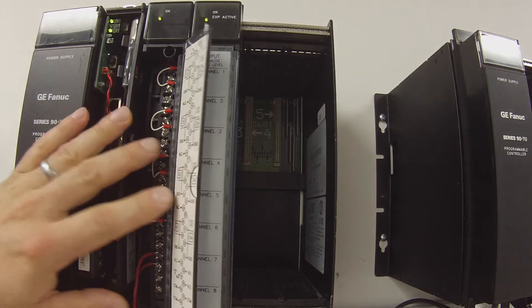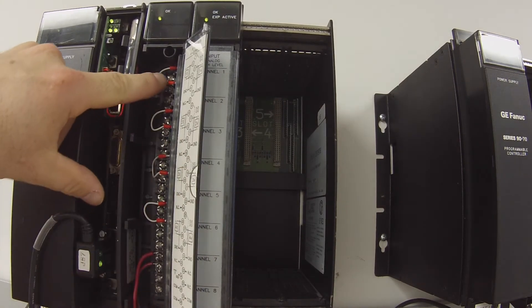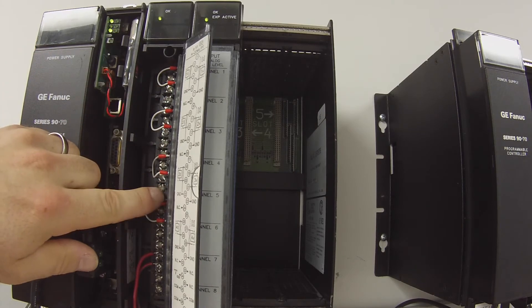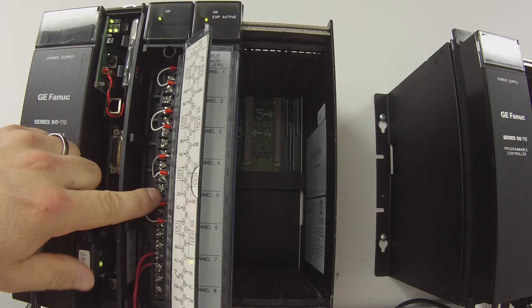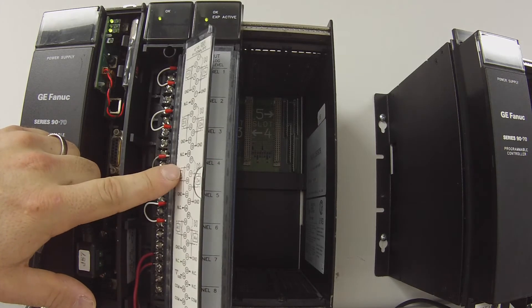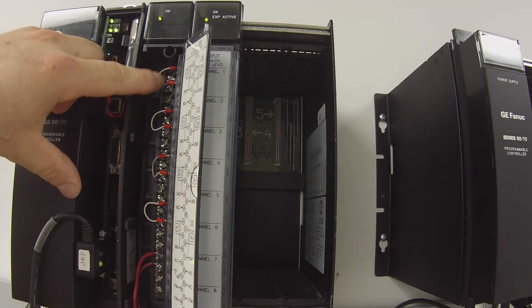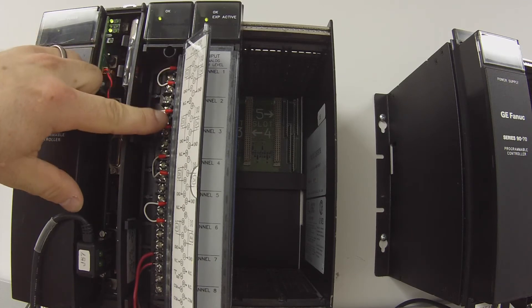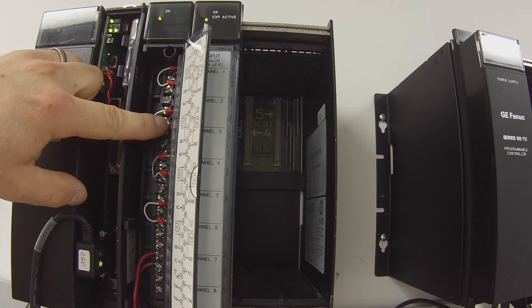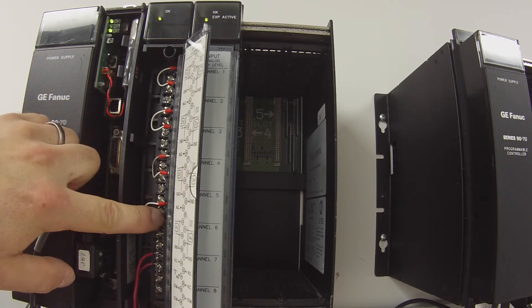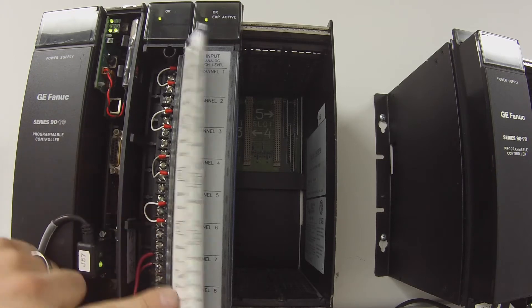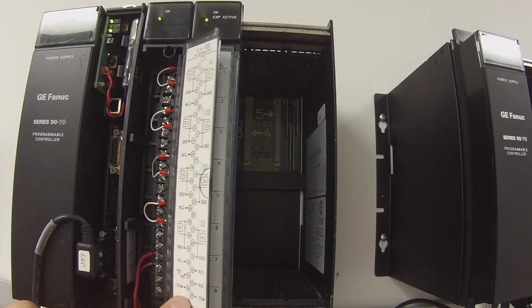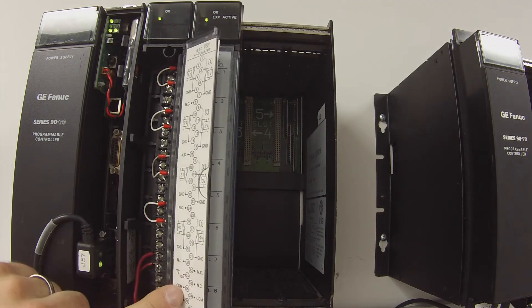First pay attention to what I have here. This terminal strip is set up so I can do either a voltage test or a milliamp test, 0 to 10 volts or 4 to 20 milliamp. I have jumpers on 1 and 3, 9 and 11, 17 and 19, 25 and 27. And for my milliamp test coming up soon I have 24 volts connected to screws 34 and 36.